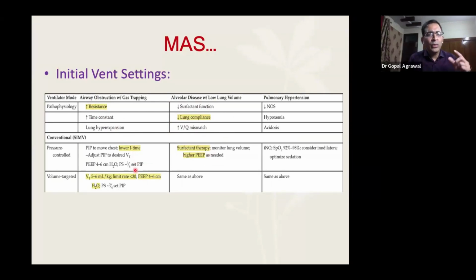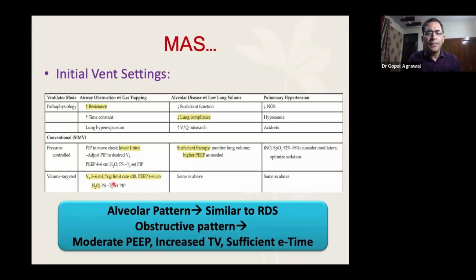Here, you need to give low rates, low I time, and sufficient E time, expiration time, so that air goes out. You need to give sufficient PEEP so that the airway doesn't collapse. Because MAS with gas trapping has dead space, you need to increase the tidal volume. So here: low I time, low rates, moderate PEEP, with slightly increased tidal volume to compensate for the dead space.